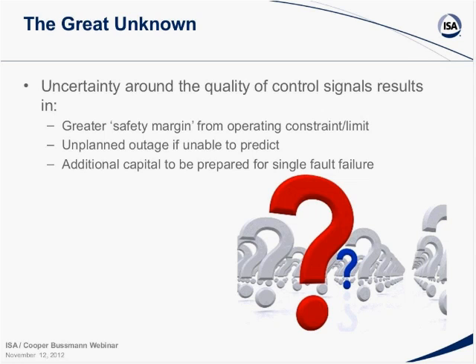How many times, with a traditional analog signal, have you been running on a signal that's bad or failed and had no way of knowing it because the 4 to 20 signal froze? With a digital signal, whether wireless or fieldbus—especially wireless—as soon as you lose that signal you know it, because nothing is coming in. You get a bad signal indication.